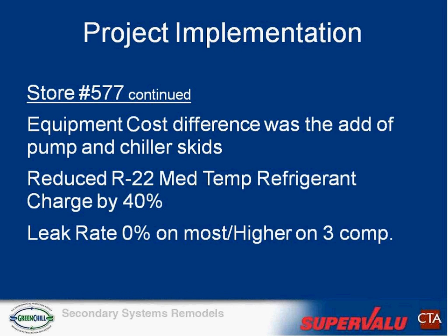As far as extra cost on equipment, it really was just the difference in the pump skid and the chiller skids, and depending on manufacturer and buying power, that would range - so I didn't list any costs there, but that's really the only added equipment cost. In this store we stayed with R22, and we were able to reduce the charge by 40% in the store, so we have these multiple systems.